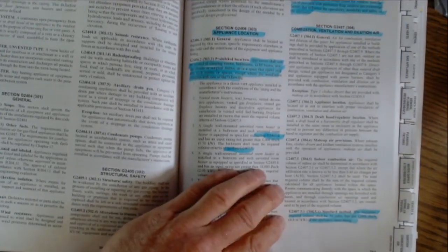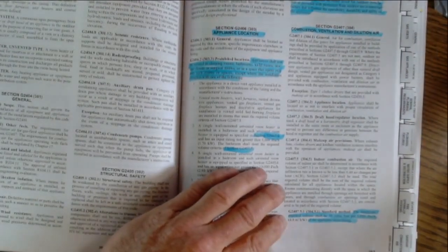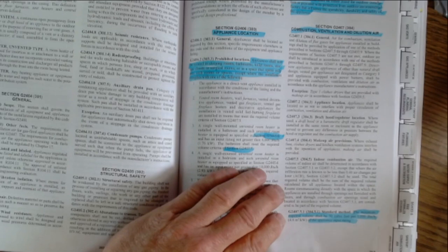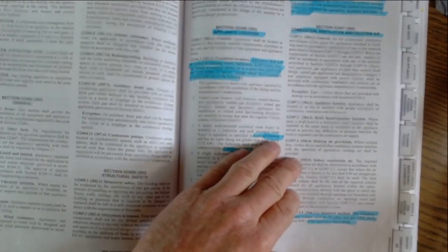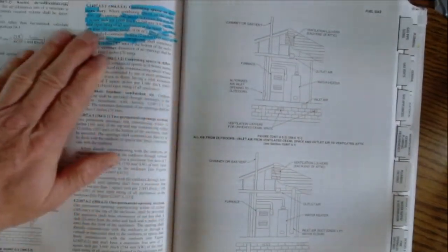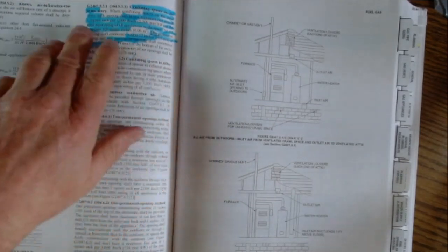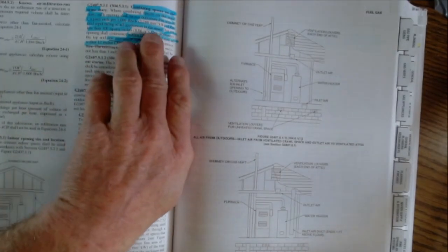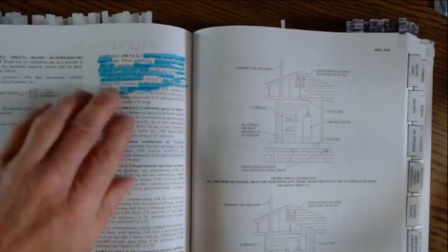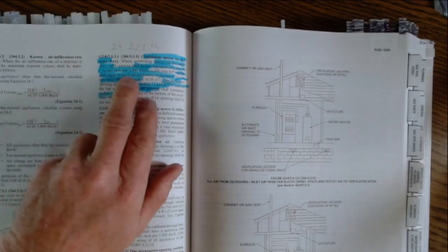But okay, so venting. If you're going to have the building self-vented, you have to have 50 cubic feet of volume in your airspace per 1,000 BTU, if you're not going to have a specific vent or a room that has a specific opening to the outdoors. So you can actually vent without having an opening to the outdoors, but it has to be that 50 cubic feet per 1,000 BTU.